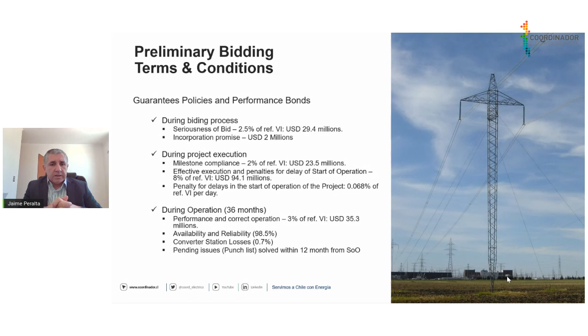Finally, we have guarantees during operation, which are performance-type guarantees, also for correct operation, that's 3% of the VI. It's basically focused on three aspects: availability and reliability, which has to be 98.5% measured on a per year basis; converter station losses, no greater than 0.7%; and also closing all pending issues, known as the punch list, within the first 12 months of operation.